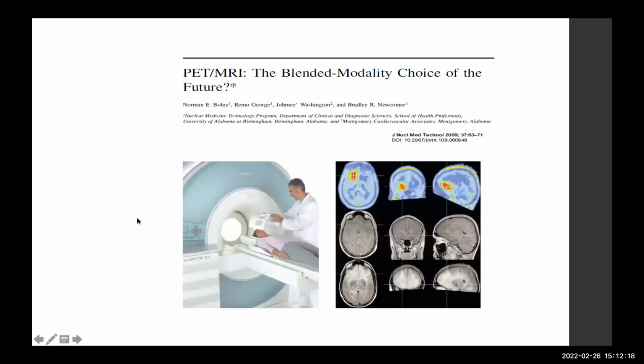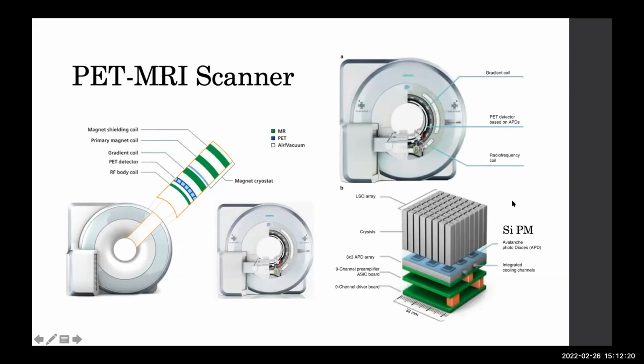Now, the photomultiplier tubes were very difficult to function in the high magnetic field. So special photomultiplier tubes, which are called avalanche photodiodes, APD, or nowadays, which is current generation PET MRI using a silicon photomultiplier, SiPM, are being used, which work in high magnetic field, and there is no problem for data acquisition for PET. So you have a LSO crystal here.